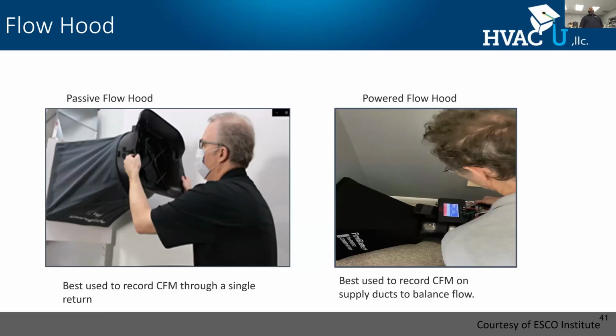Let's talk about the flow hood. All right, flow hood's purpose: it's a device that's going to capture the CFM. All right, you're going to read CFM directly. It's calculated because the dimensions of that flow hood are known. So it's based on CFM through a supply or return. And there's two types. A passive flow hood is just that, it's just going to capture it. A power flow hood is actually a little bit more accurate because it has a fan that's going to reduce the pressure drop of the flow hood. In either case, using these will help you identify problems.